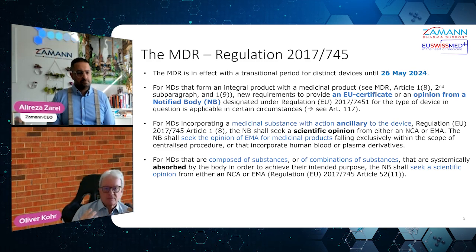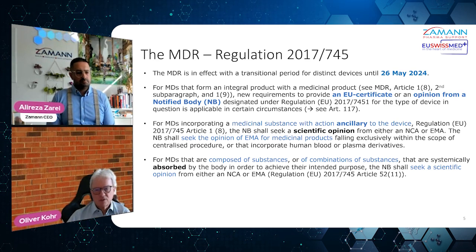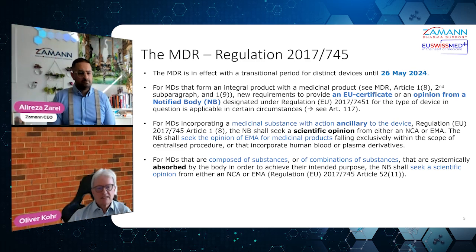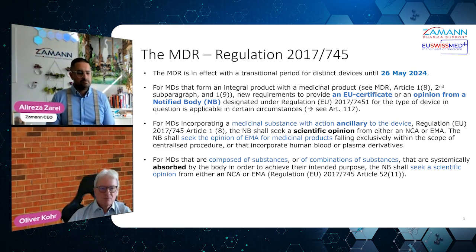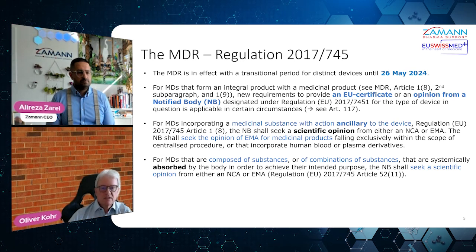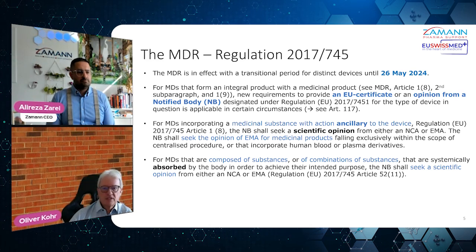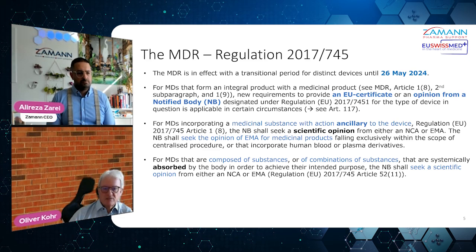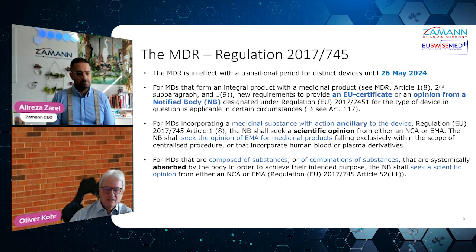And there are some aspects mentioned in Article 1, and I'll put that down here, 1(8). The key thing is that in the case of the integral product, this integral approach, a product with a medicinal product, you would need an EU certificate, or, now comes the point, an opinion from a notified body designated under the MDR for this type of question. Why designated is a very key word.